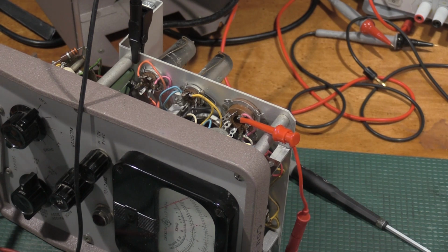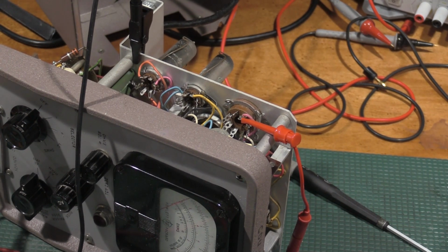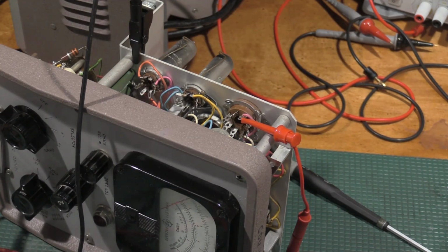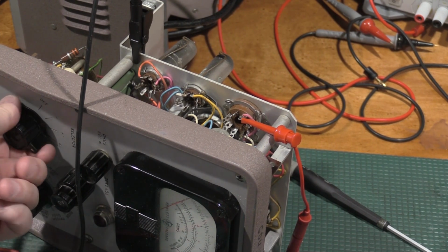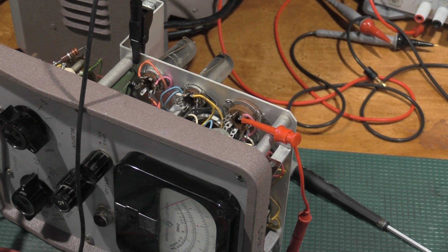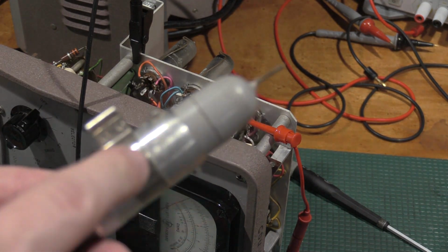The manual says it should start at 2 and then slowly climb till it goes up to 4. And mine's hanging around 2.2, so it's not climbing like it's supposed to. I don't see any shorts, like moving the cable and stuff like that. It's not causing me any problems. But yeah, it's not causing me any issues. I was just checking on the AC, see if the reading changed. It did not.